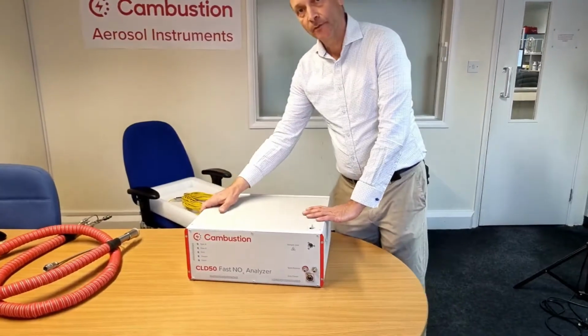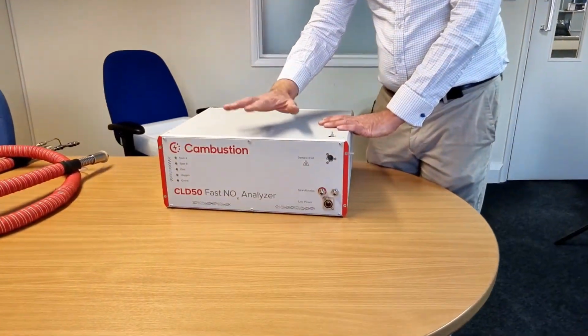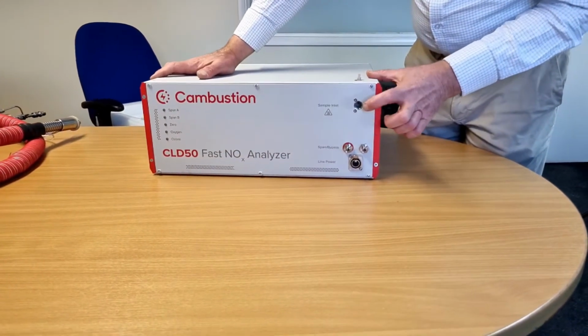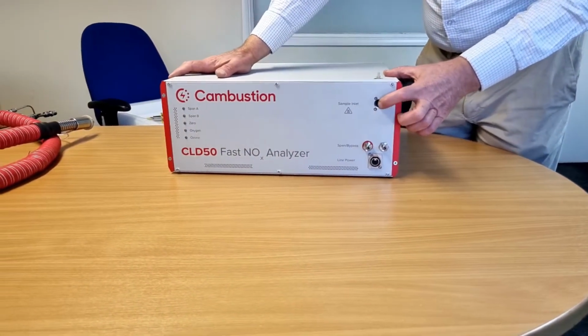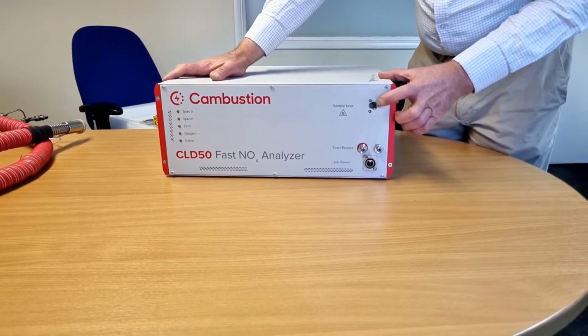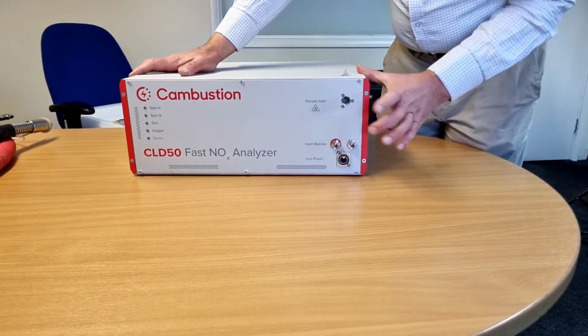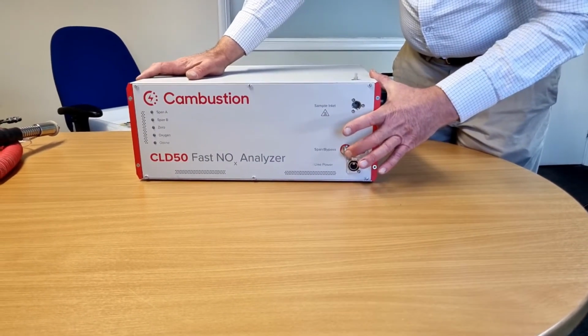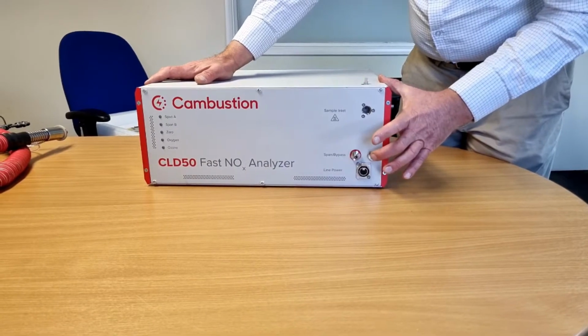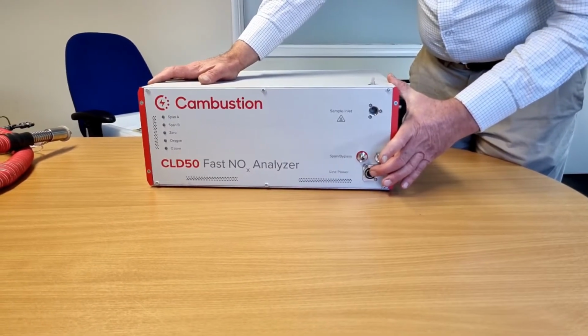I'll now show you some of the features and the fittings on the analyzer itself. So on the front panel we've got the sample inlet here. This is where you will fit your sample line. There is also, for some applications, a span 0 outlet and a bypass, and there's the electrical connector for the heated sample line.